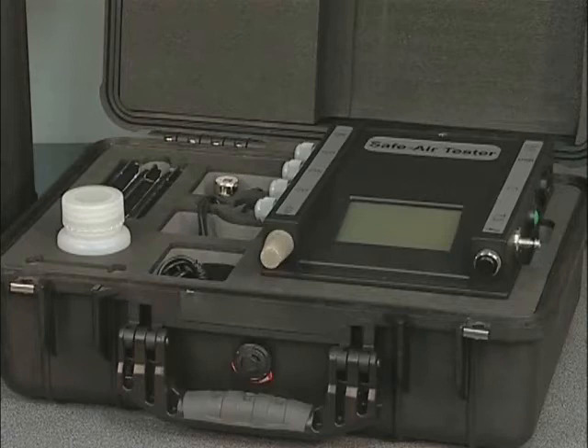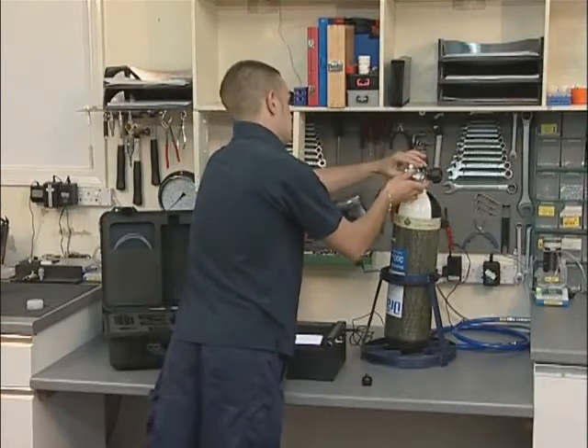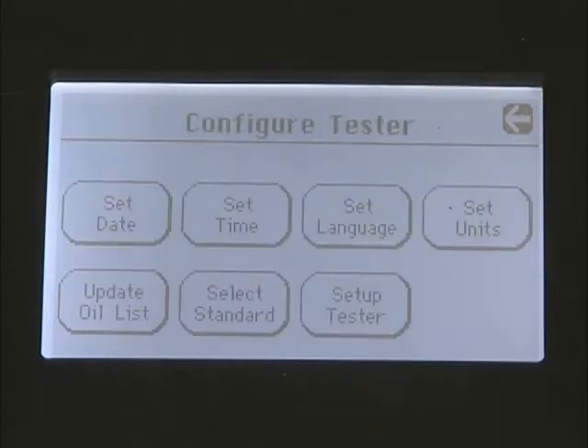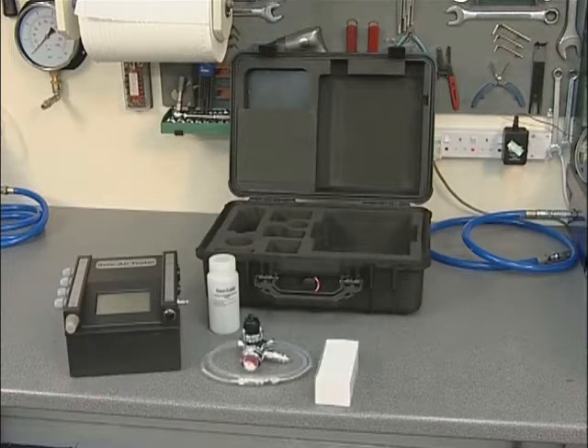This training session features the F4001, which is designed specifically to test high pressure charging systems up to 300 bar. The F4001 has a touch screen display and is supplied in a hard weatherproof case with storage provision for a wide range of accessories and equipment.